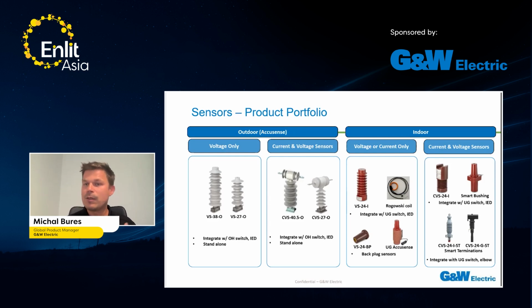Also, we are constantly developing, thanks to our own R&D, new devices. For example, the new one, underground AccuSense, can also be immersed in water and simply performs the same. So as I mentioned, we have standalone units which can be installed on the overheads, and standalone units which can be installed for the air insulated switchgear and gas insulated switchgear. For example, you can see the VS24BP, it's a backplug for the cable connector, same as the underground AccuSense. We have the smart bushing, which is perfect for the gas insulated switchgear and can replace the standard bushing, so you can have the same device but with the smart functions.